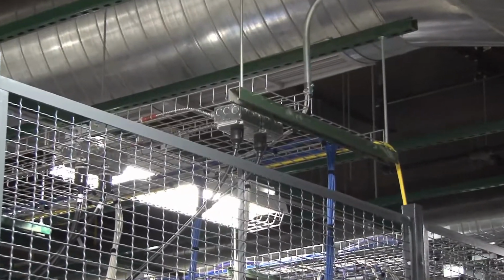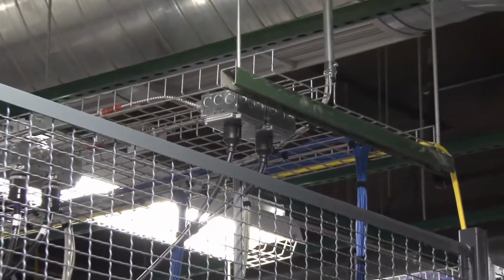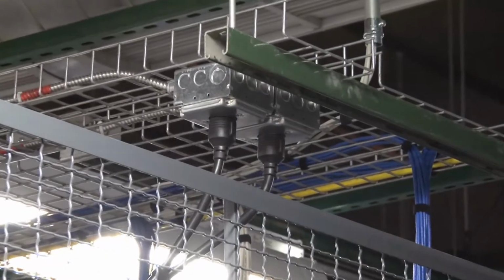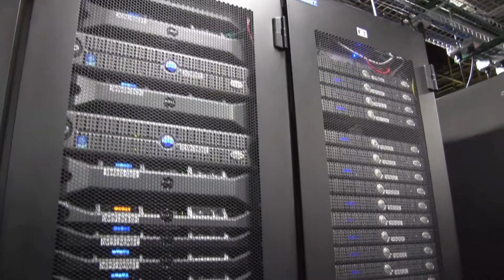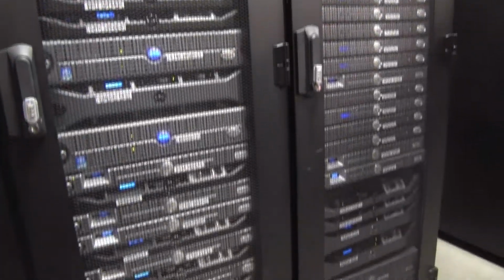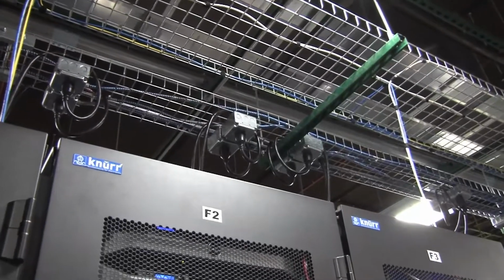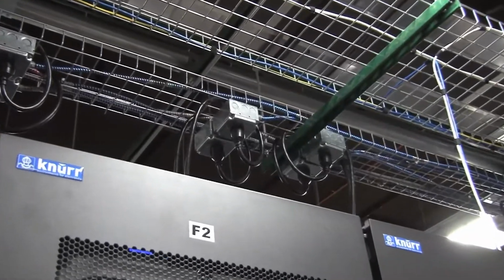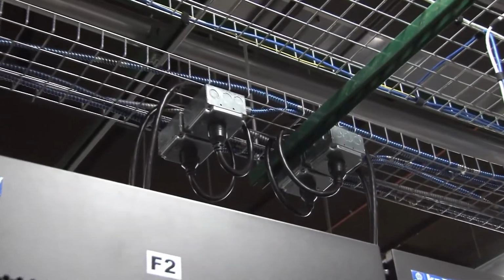Involta uses an A-B supply system to each and every rack. Most of the IT equipment has dual power supplies. That is 2 power supplies within a chassis or within a server. We plug one of those into A and one of those into B. So you always have 2 sources of power. If something were to disrupt one source of power, the other source of power would go on ready to serve.